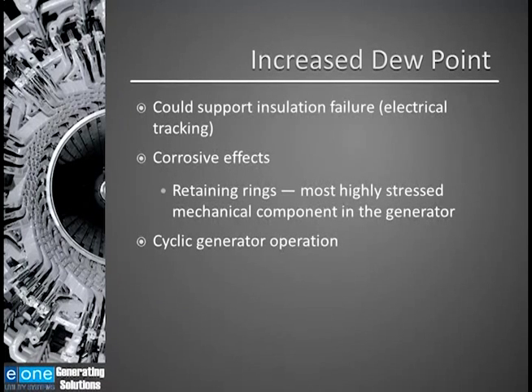With base load generators, you have a constantly warm temperature in the generator, so condensation really doesn't form in these units. However, with peaking units, where you're cycling the generator, this can result in temperature fluctuations, which can result in condensation forming in the generator.